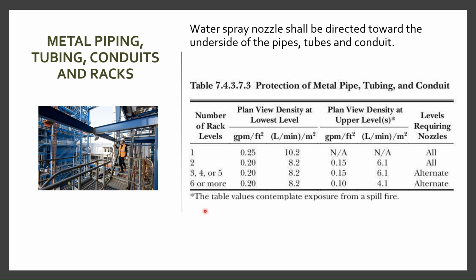Here it is mentioned as the number of rack levels: 1, 2, 3, 4, 5 or 6. Here the design density at the lowest level is 0.25 GPM per square feet, and it is reduced to 0.20 GPM per square feet if you have 6 racks or more. And the design density at the upper level shall be 0.15, 0.1. All this will be discussed in future classes. At this point of time, just remember metal piping, tubing, conduits and racks may require water spray fixed protection.